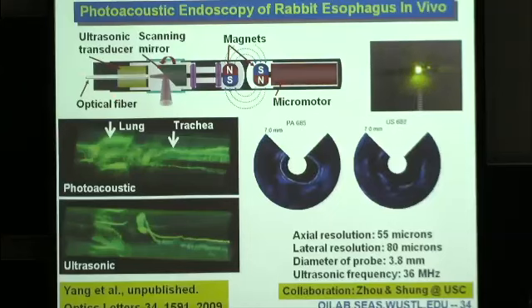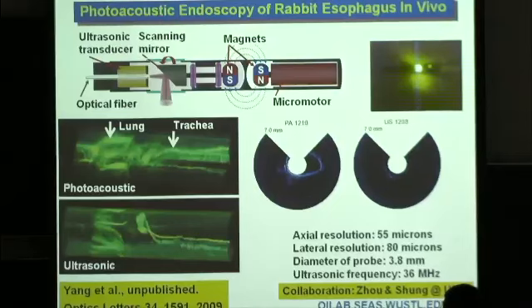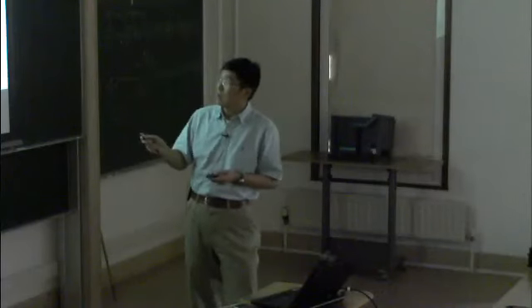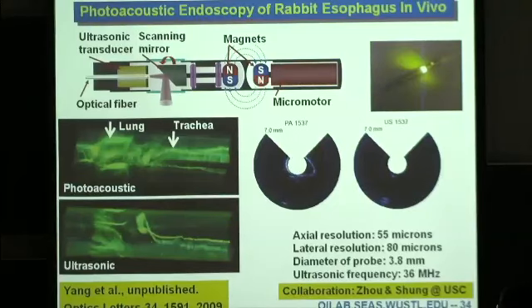We transport light through this optical fiber. Light is reflected by this mirror onto the tissue you want to image. And the photoacoustic wave comes back, reflected by this mirror surface, received by this ultrasound transducer. So ultrasound transmission does not like air. This chamber, as a result, is liquid filled. The micromotor does not like liquid, so this side of the chamber is hermetic. We separate the two chambers, but transfer the torque through a pair of magnets.